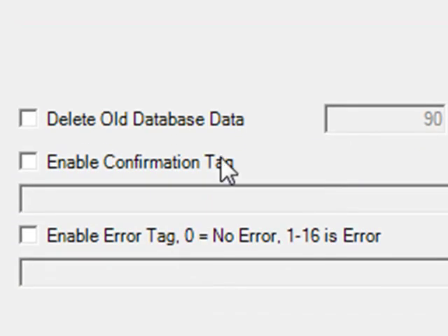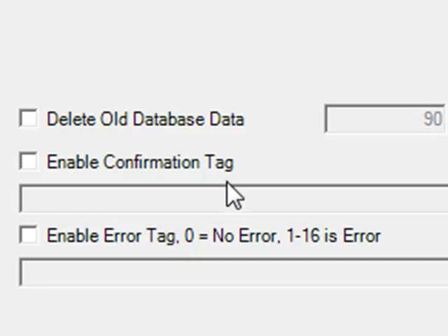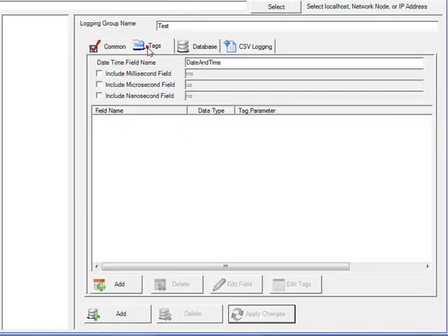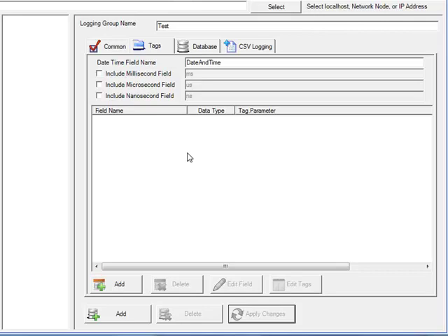And for PLC queued data, we can enable confirmation and error feedback to tell the PLC or data source that the data has been successfully logged, or if there was an error, to retry. This is commonly used with the event-driven logging type. Under the tags tab is where we define the data sources that we want to log for this logging group.